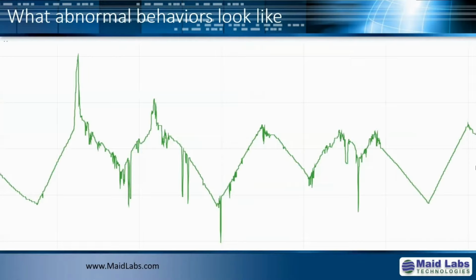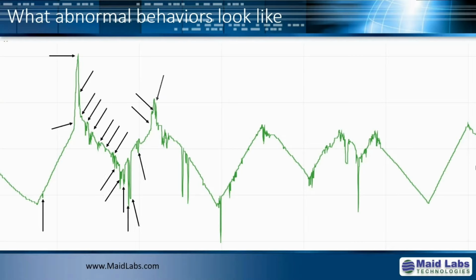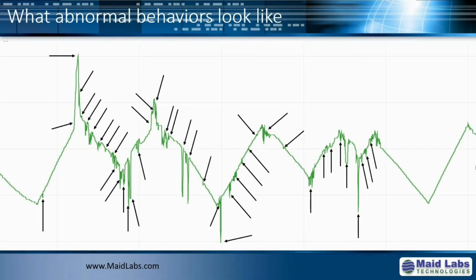Okay, and if you click next, you will probably see all these abnormal behaviors that are going on at that level. These came from a lift station where you would expect the pumps to start and stop at the same level all the time. You can see that the water, no way water works this way. I mean, you know that. But that lift station was connected to a SCADA system that was not reporting any kind of alarms, because it was never at a level that was high or low enough, for long enough, to generate an alarm.